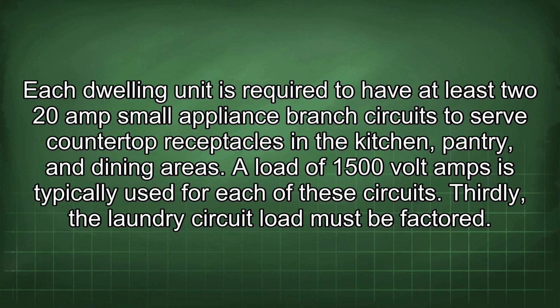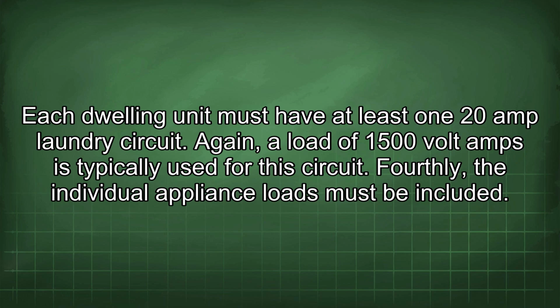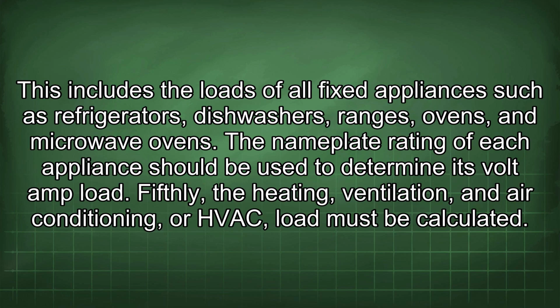Thirdly, the laundry circuit load must be factored. Each dwelling unit must have at least one 20-amp laundry circuit. Again, a load of 1500 volt-amps is typically used for this circuit. Fourthly, the individual appliance loads must be included. This includes the loads of all fixed appliances such as refrigerators, dishwashers, ranges, ovens, and microwave ovens. The nameplate rating of each appliance should be used to determine its volt-amp load.